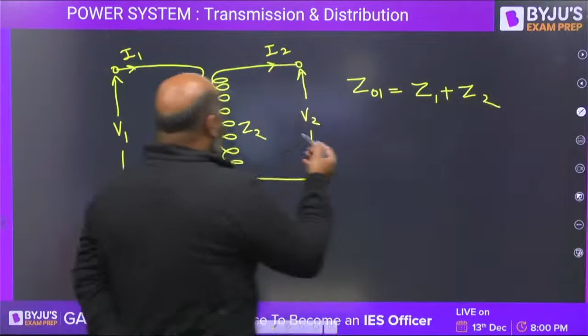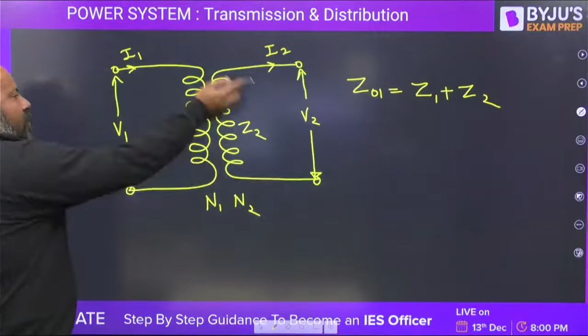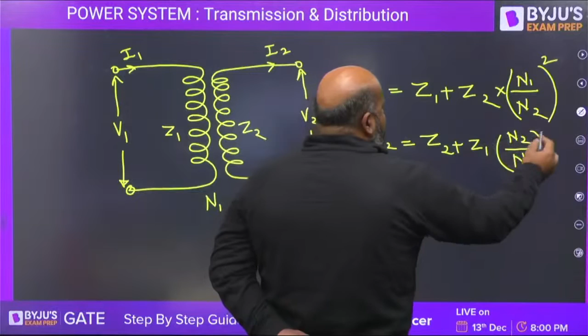So it becomes Z1 plus. Because you are referring Z2, Z1 will be as it is. You are referring Z2 from secondary to the primary, so Z2 has to be normalized: from where you are coming, divide by the number of turns, to where you are going, number of turns, and do the square. Similarly, if you want to find the total equivalent impedance referred to the secondary side, you can write the secondary side impedance as it is, plus primary side impedance multiplied by N2 upon N1 to the square.